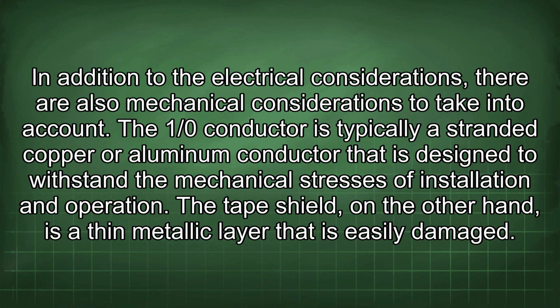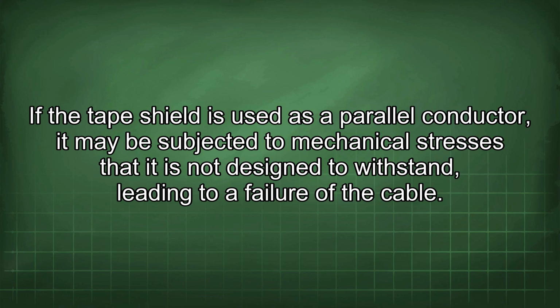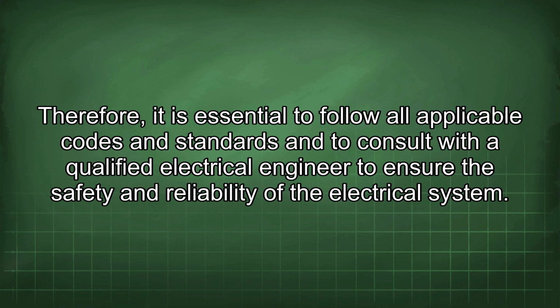In addition to the electrical considerations, there are also mechanical considerations to take into account. The 1/0 conductor is typically a stranded copper or aluminum conductor that is designed to withstand the mechanical stresses of installation and operation. The tape shield, on the other hand, is a thin metallic layer that is easily damaged. If the tape shield is used as a parallel conductor, it may be subjected to mechanical stresses that it is not designed to withstand, leading to a failure of the cable. Therefore, it is essential to follow all applicable codes and standards and to consult with a qualified electrical engineer to ensure the safety and reliability of the electrical system.